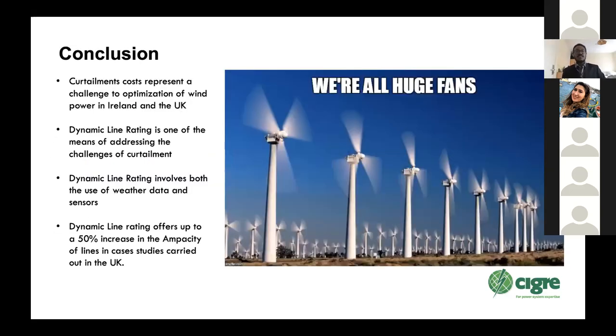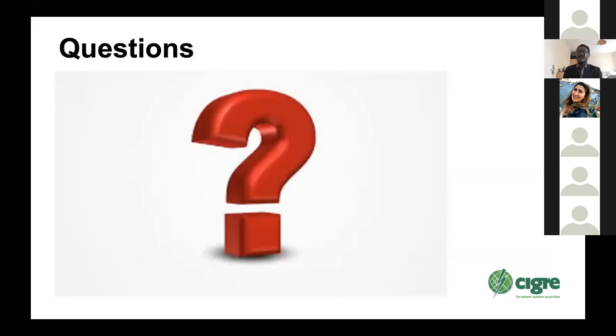So just to provide you a quick summary, curtailment represents a drain on and a challenge for optimizing wind energy both in Ireland and the UK. However, dynamic line rating is potentially one of the means of addressing this issue. Dynamic line rating is done through the use of both weather data and sensors placed along the length of the line. And as you saw in the case study, dynamic line rating offers up to a 50% increase in the ampacity of the line. And I think at the end, we're all huge fans of this technology. Thank you. Any questions?